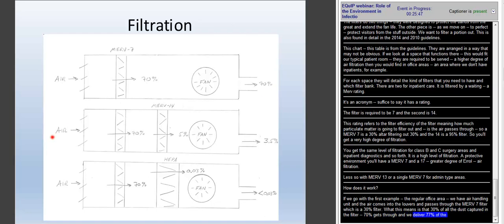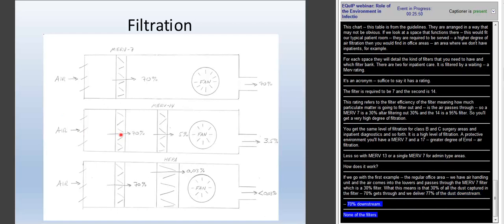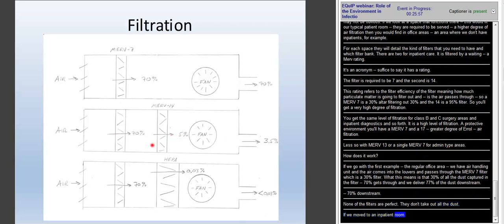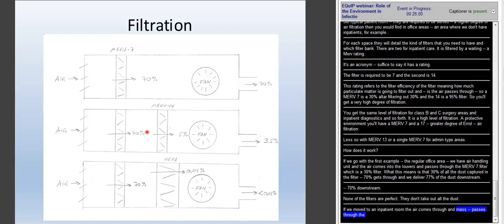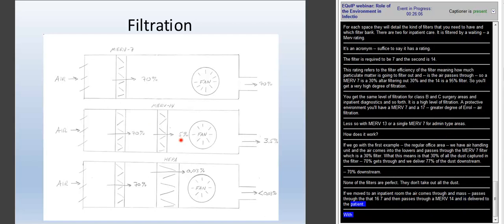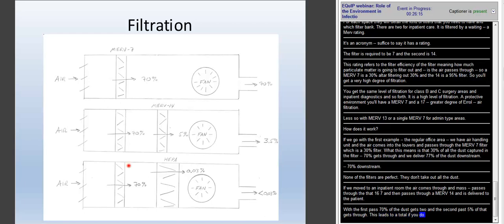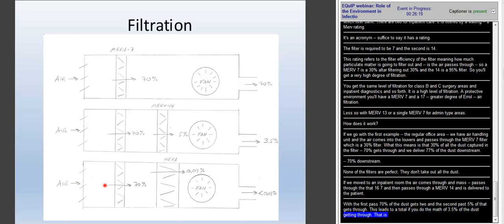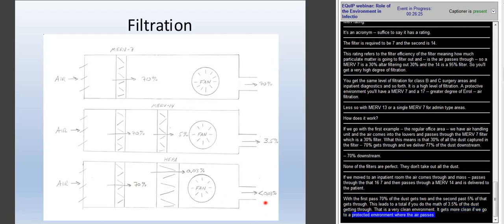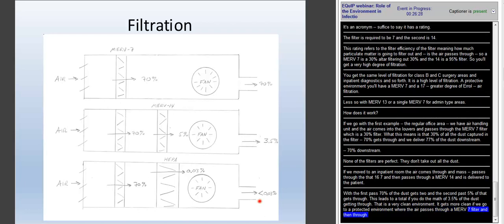If we move up to an inpatient room, the air comes through, it passes through the MERV 7 pre-filter, it then passes through a MERV 14 filter, and then is delivered to the patient. So through the first pass, 70% of the dust gets through. Through the second pass, because a MERV 14 is a 95% filter, 5% of that gets through, leading to a total, if you want to do the math, of 3.5% of the dust getting through. But that's a very, very clean environment. It gets even cleaner if we go to a protected environment where the air passes through a MERV 7 filter and then through a HEPA filter, and less than 0.03% of the dust that's in that air gets through. So we have these degrees of filtration.